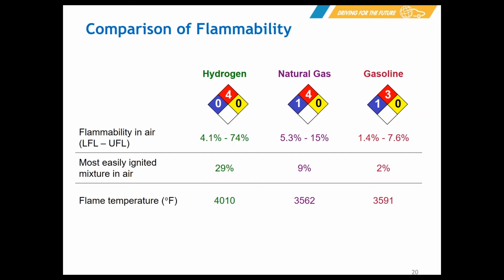If leaks were significant enough to reach concentrations of around 2% hydrogen, systems are designed to shut down and isolate themselves. For example, if someone was fueling at a station and a leak was detected in the dispenser cabinet, the station would stop the fueling, isolate the various processes, and shut itself off safely. The most easily ignited mixture of hydrogen, which takes the least amount of energy to ignite, is quite a bit higher than for those other fuels.